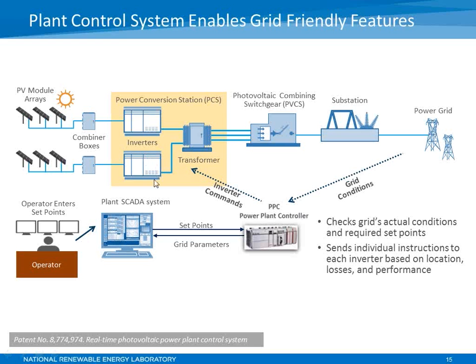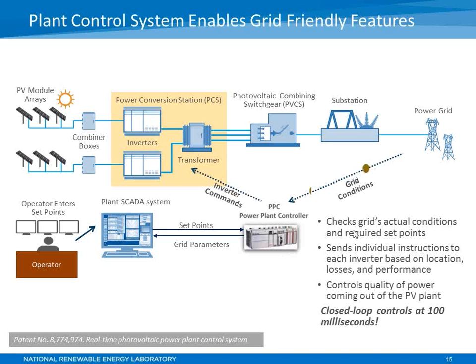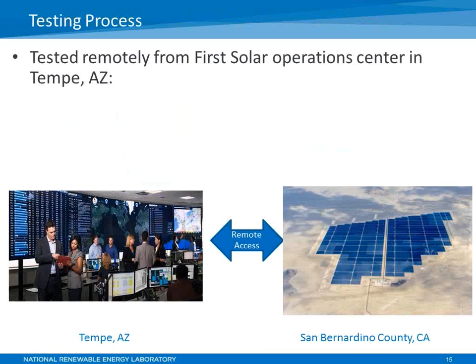This is because in general, each of the inverters sees different conditions based upon the irradiance and the DC collection system, etc. In essence, this is a closed loop control system, so that we can use it to control the output of the power plant. And this closed loop system performs at 100 millisecond loops, so that we can control the output of the plant in a much faster manner than is sometimes possible with other kinds of generation.